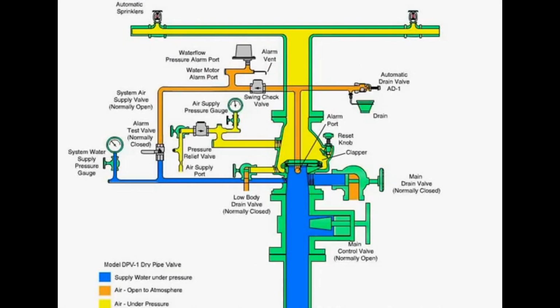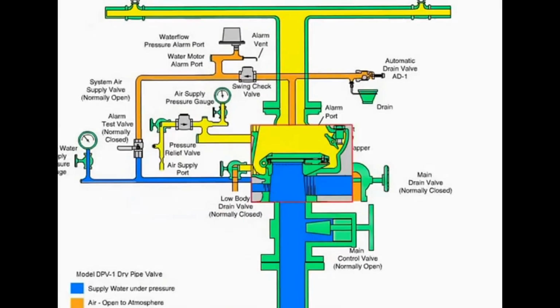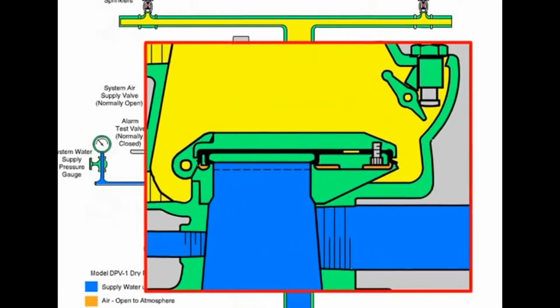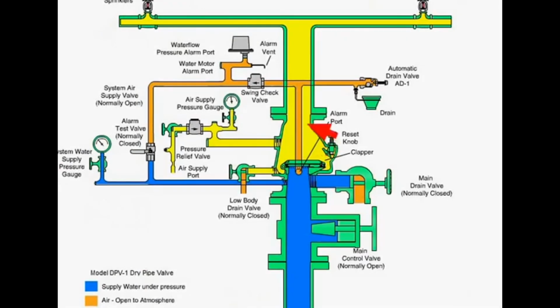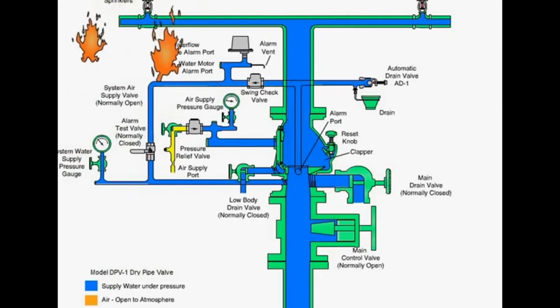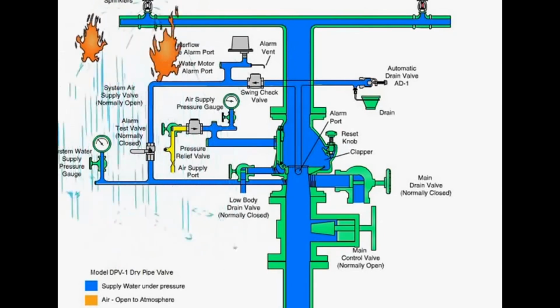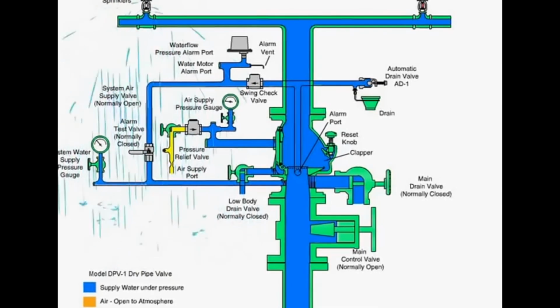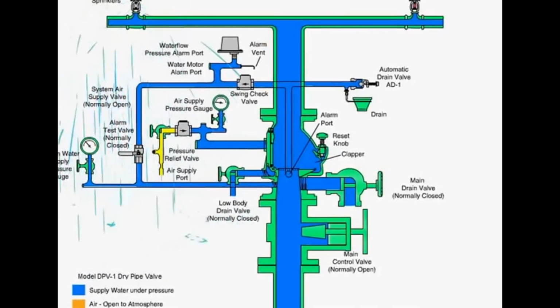The sprinkler pipe contains air under pressure, shown here in yellow. The water supply contains water under pressure, shown here in blue. The area located just beneath the clapper is open to atmosphere through the alarm port and the pipe connections to the automatic drain valve and alarm devices, shown here in orange. When a fire activates a sprinkler, the air under pressure in the sprinkler piping is released. The valve opens, allowing water to spray out of the sprinkler. Water will only spray out of sprinklers that have been activated by the fire. Water will also flow through the alarm port to the alarm devices to indicate water flow.